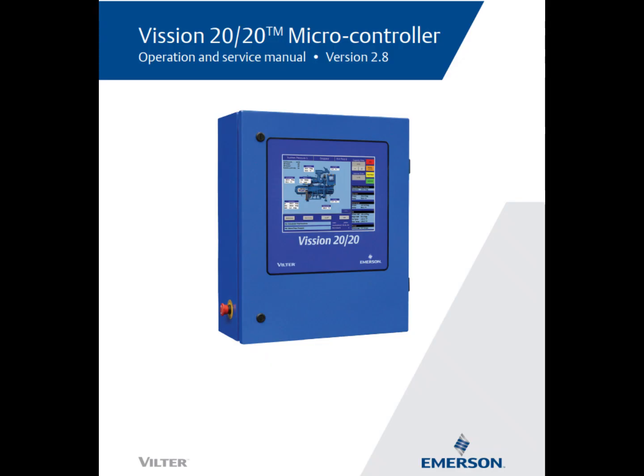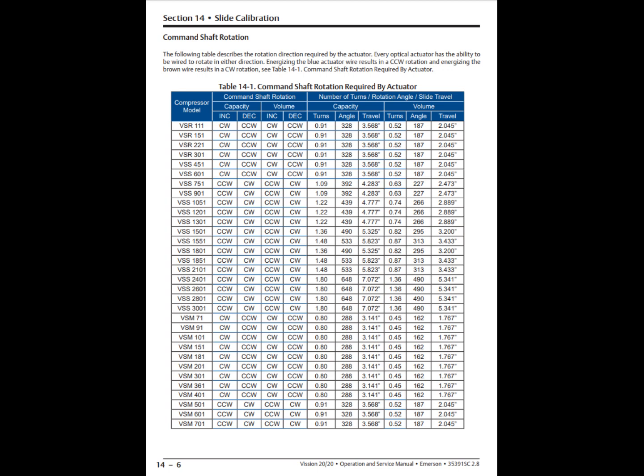You can verify the correct rotation for your capacity and volume actuator by going to the Vilter manual or by pressing the Help button on the Vision 2020, then selecting Slide Valve Calibration, then pressing the next button until you reach this page showing our compressor models and rotation of the command shaft for capacity and volume actuators. This page will also show you the rotation angle for each capacity and volume slides. This later can become helpful when trying to troubleshoot your volume and capacity slides by verifying the distance traveled of your command shaft.